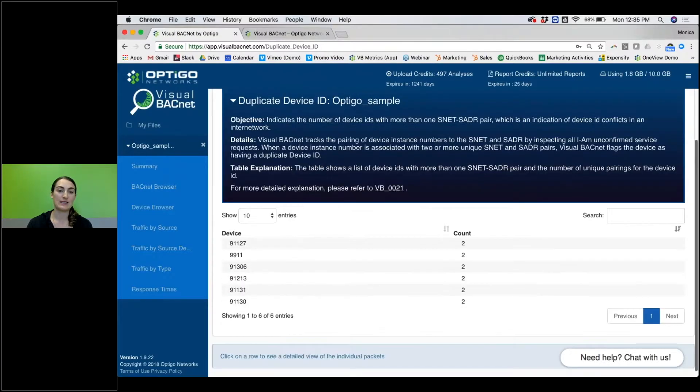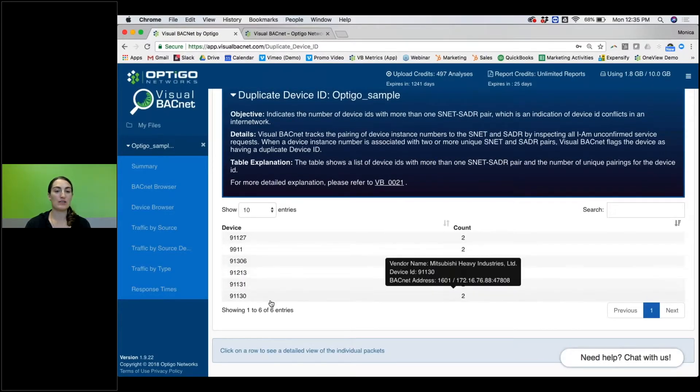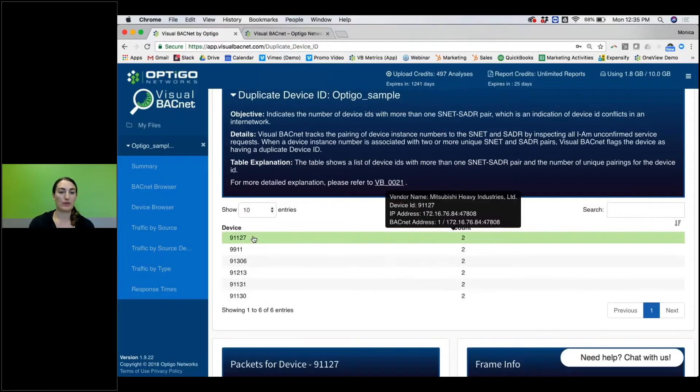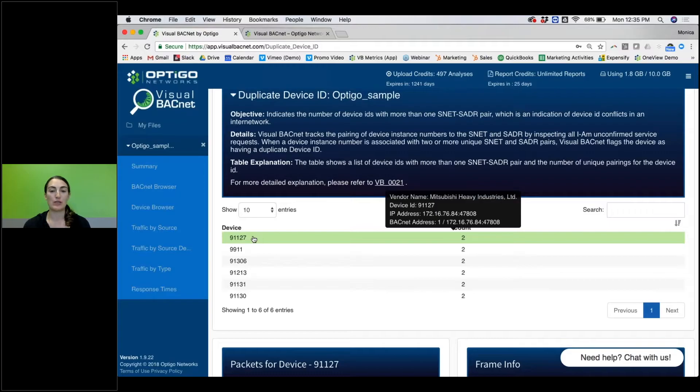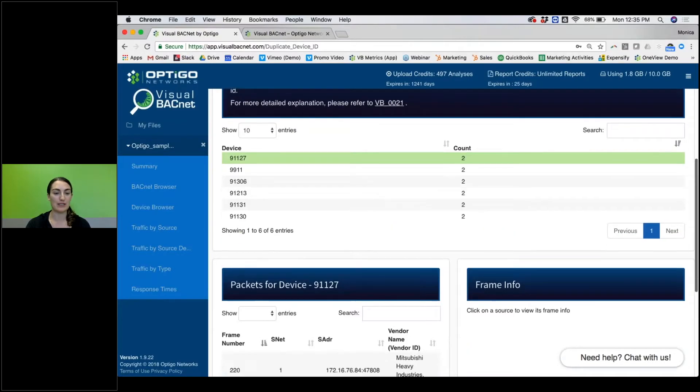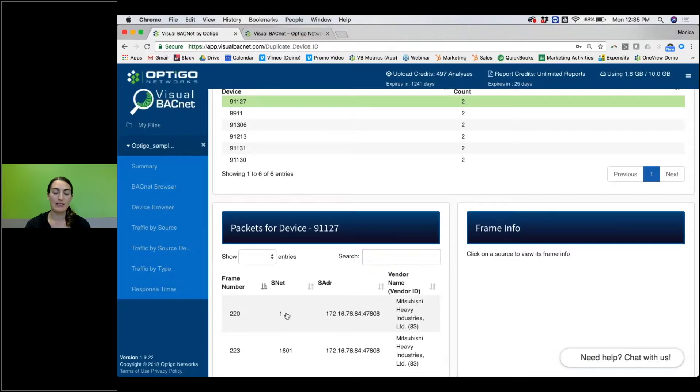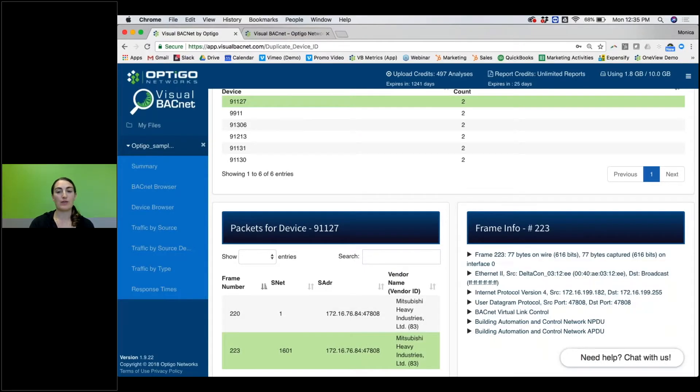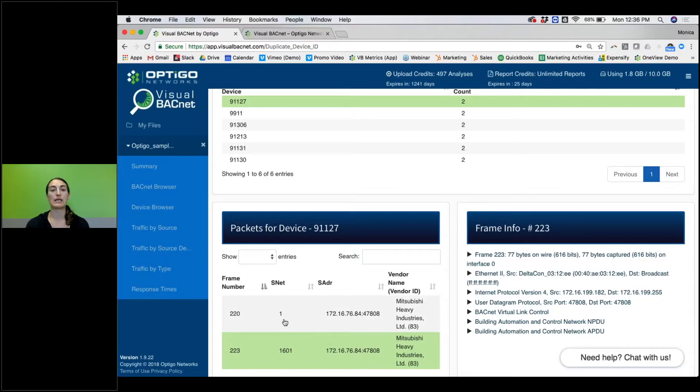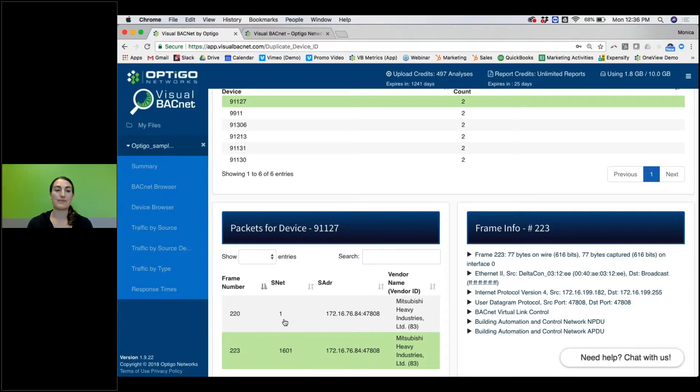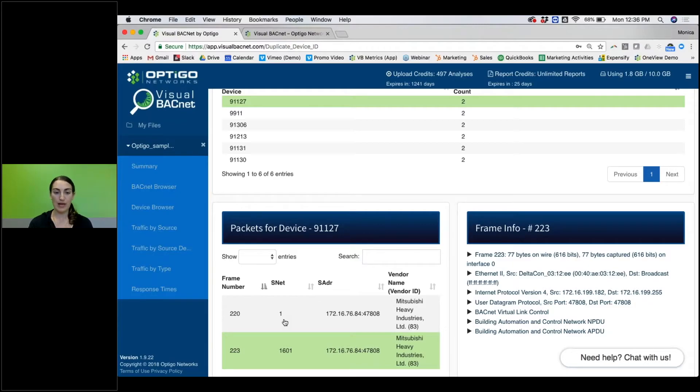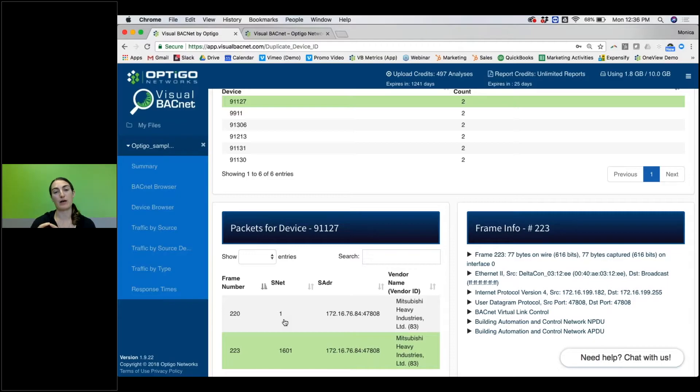Here you can see all six duplicate device IDs. For example, device 91127 exists on both. We scroll down, we can see it's on subnet 1 and subnet 1601. You can click on that if you'd like to get the actual Wireshark frame, but realistically you can take that and go, okay, on my device list, device 91127 should only be on network 1601. I need to go find the one that it's configured that way on network 1 and change it to the appropriate device list or device ID.